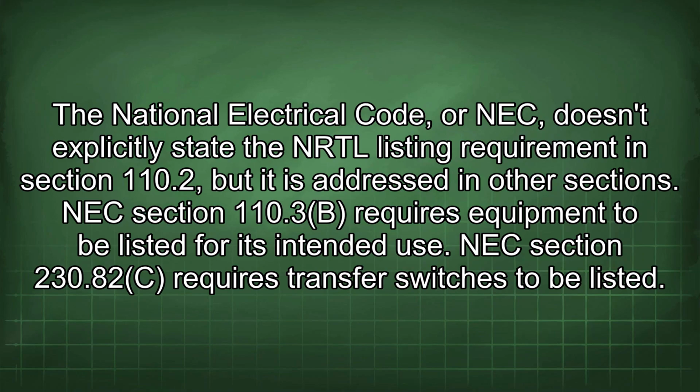The National Electrical Code, or NEC, doesn't explicitly state the NRTL listing requirement in section 110.2, but it is addressed in other sections. NEC section 110.3(B) requires equipment to be listed for its intended use. NEC section 230.82(C) requires transfer switches to be listed.